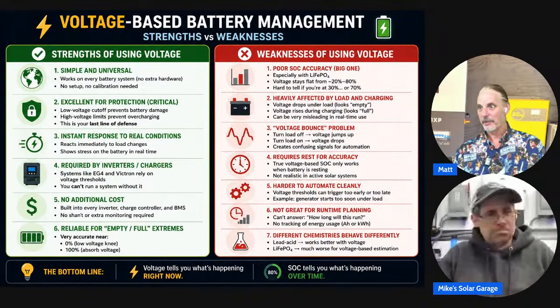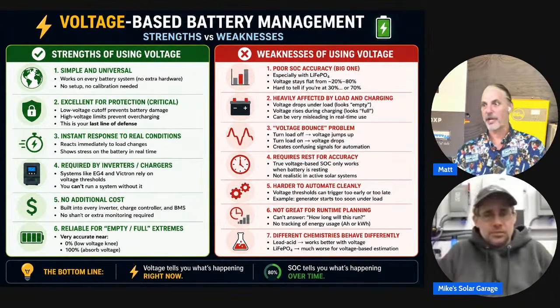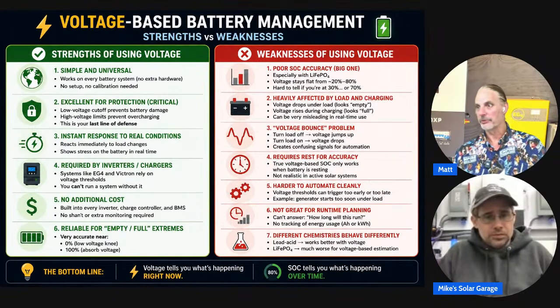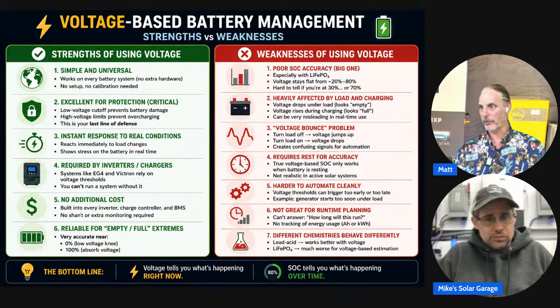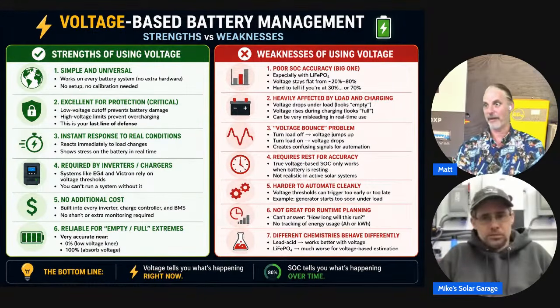I went through quickly the strengths and basically just covered: it's excellent for protection, instant response to real conditions, meaning when everything gets into absorption mode or float mode, and if you have multiple chargers from multiple different sources, they're able to respond easier and better. They're not worried about state of charge, they're more worried about immediate conditions on the line of the battery bus. It's required.